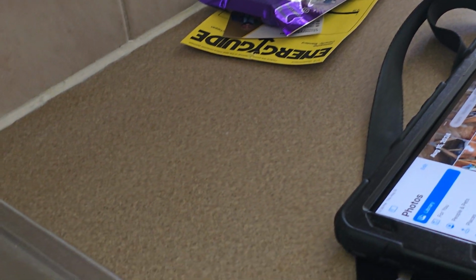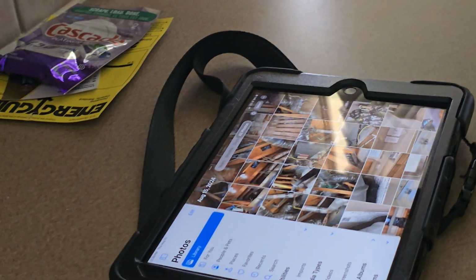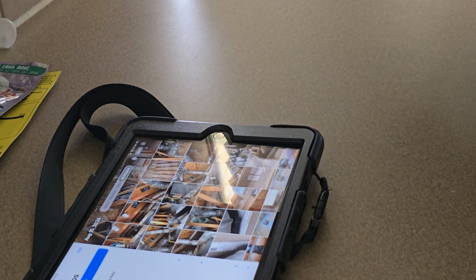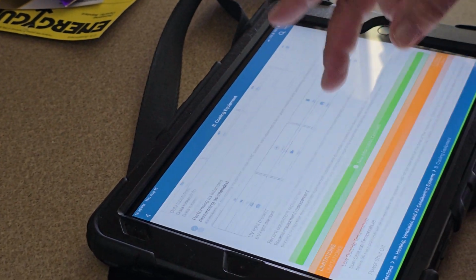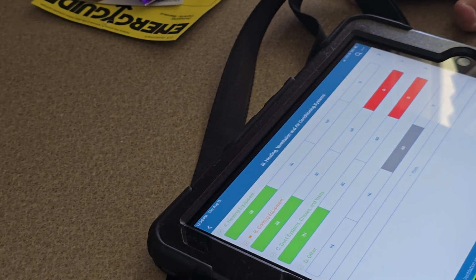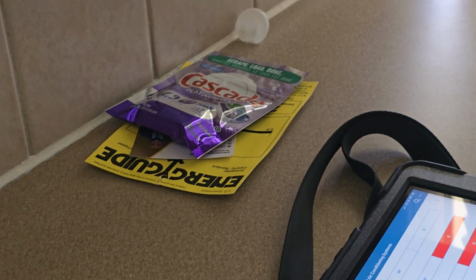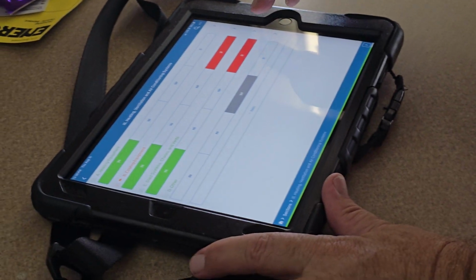Now the ductwork is overlapping, and they're in contact in a number of places. There should be a thin piece of insulation in between so it doesn't form condensate between, and that can drip into the ceiling. So basically the air conditioner is performing as intended, but there are some registers not getting the air they need, and so I think it does need to be balanced. So I'm going to recommend an HVAC balancing.